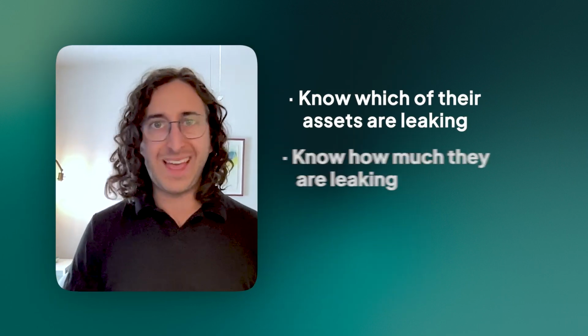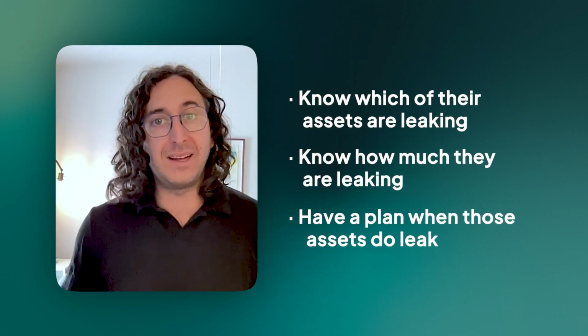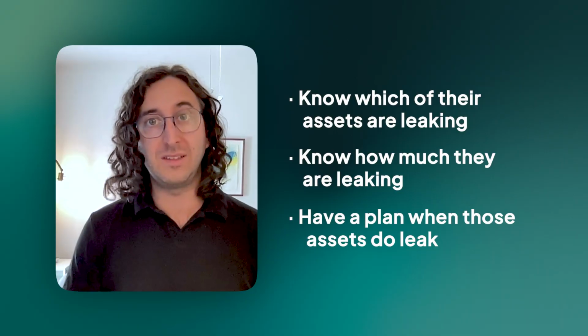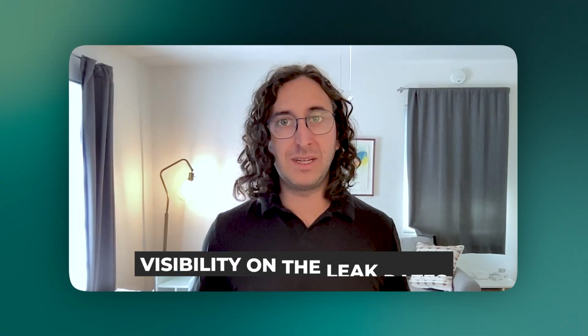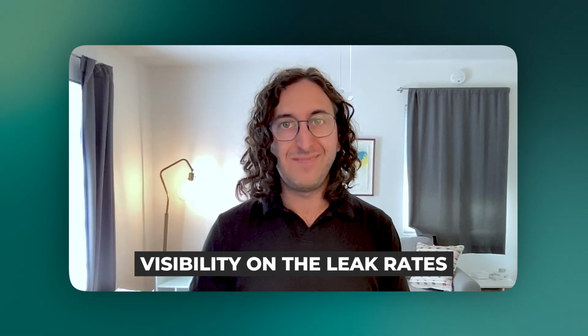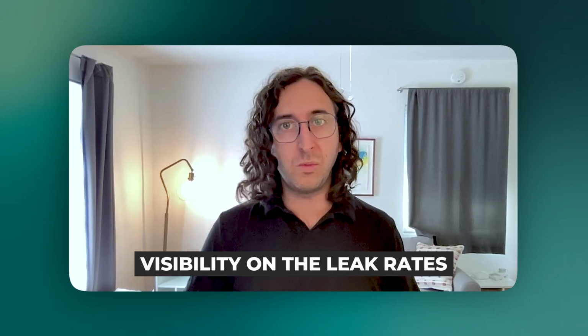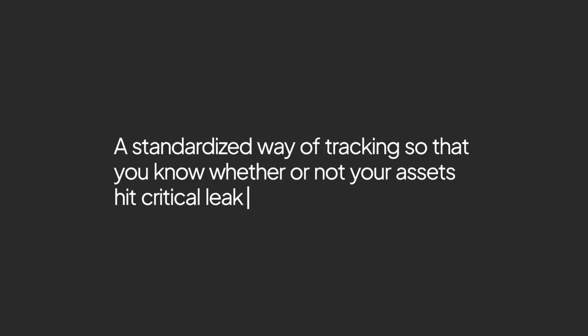To comply with this growing and complex web of regulations, operators need to know which of their assets are leaking, how much they are leaking, and to have a plan on what to do when those assets do leak. Key to that is having visibility into the leak rates of your assets. Anytime refrigerant is added or removed from a system, anytime a leak inspection is performed, you're going to want a standardized way of tracking and managing that so that you know whether or not your assets hit critical leak rate thresholds.